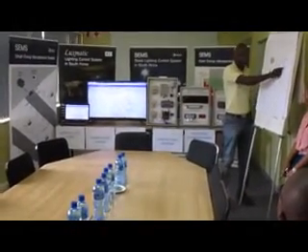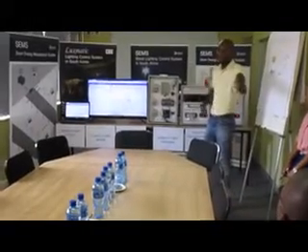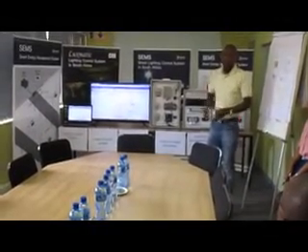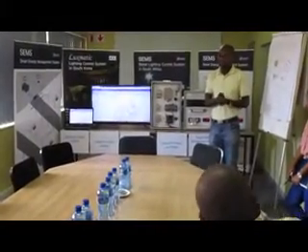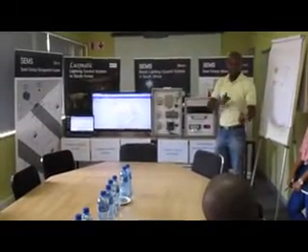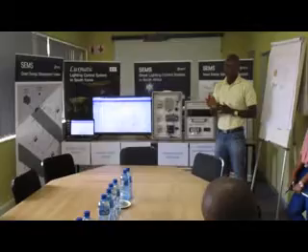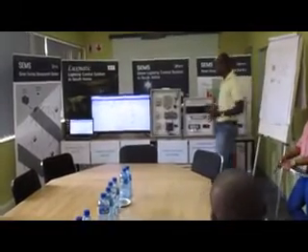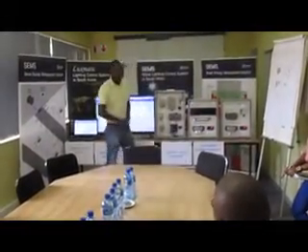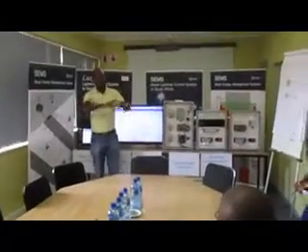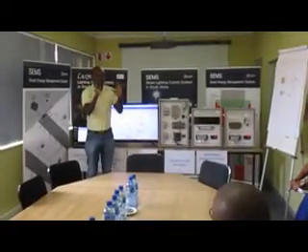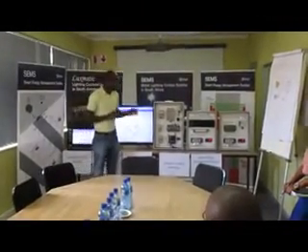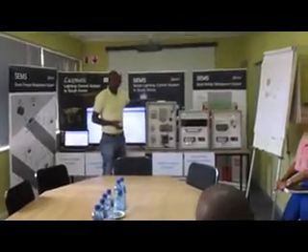So the communication is going through. We don't need to install an extra cable for the communication to go through. We're going to use the same cable to communicate. That system, we call it PLC, power line communication, is also a good part of this system, whereby we are combining communication and electrical at the same time. Besides that, I'd like to introduce you to our devices. We have a street light, the contactor, breakers, and a photocell which we normally use. The system also has some electronic components and communication components.